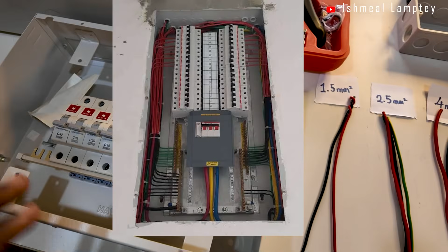It is also important for them to terminate the cables neatly within the panel. You shouldn't overcrowd this panel with too many cables. That's why there are different sizes of panels or distribution boards for each job. Have the right size of distribution board to distribute your cables evenly and avoid overcrowding, because overcrowded wires can also end up causing problems. So that's just a basic overview of the distribution board.